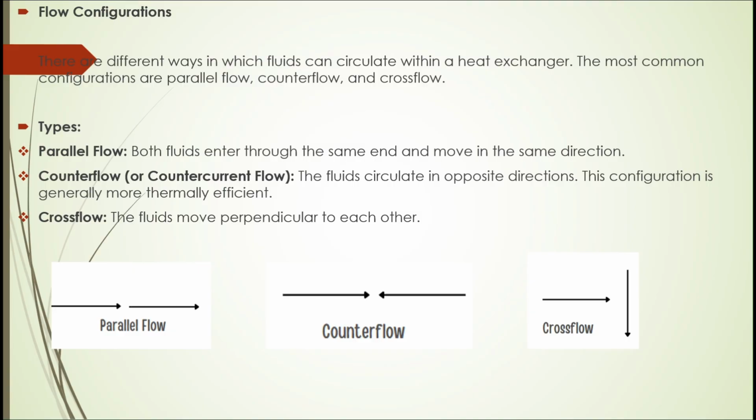Configurations. There are three main flow configurations: parallel flow, counterflow, and crossflow. In parallel flow, both fluids move in the same direction. In counterflow, they move in opposite directions. In crossflow, they move perpendicular to each other.